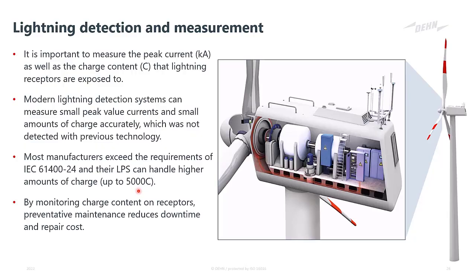And if we do this, we can apply preventative maintenance, and we reduce downtime and cost, and we also possibly avoid catastrophic failure in the case where we saw the turbine catching fire and those sorts of catastrophic damages. The system, as I said, is typically installed inside the nacelle with a Rogowski coil or CT around the shaft of the turbine, and it measures the current going through there. Some of these systems can be advanced even further, where you have units inside the blades, which have to be implemented during manufacturing, but they will even then tell you which blade was struck, and you can know exactly what blade to go and do maintenance on.